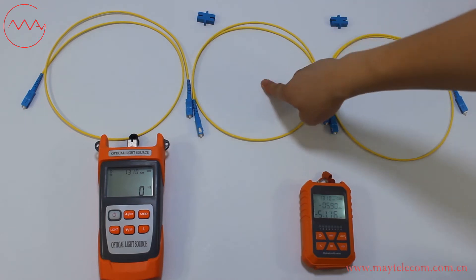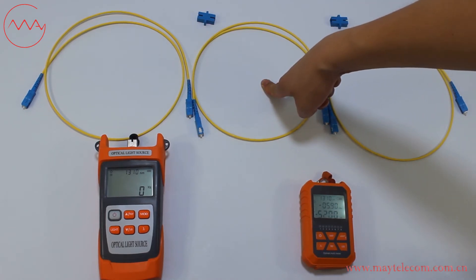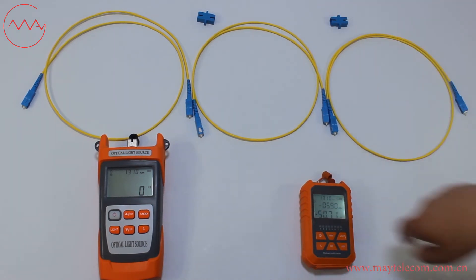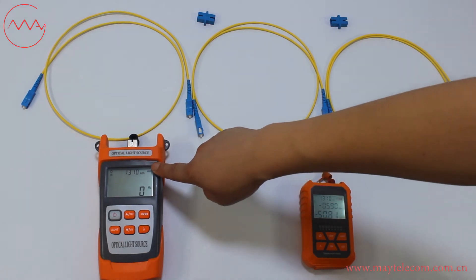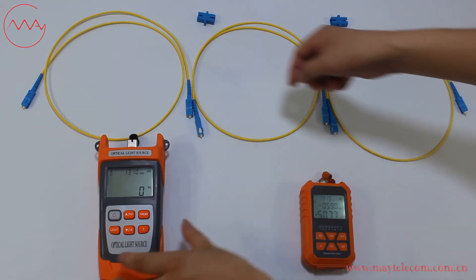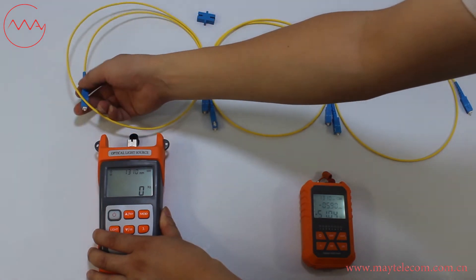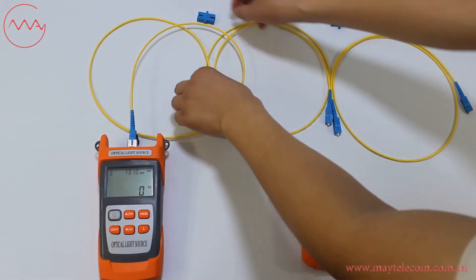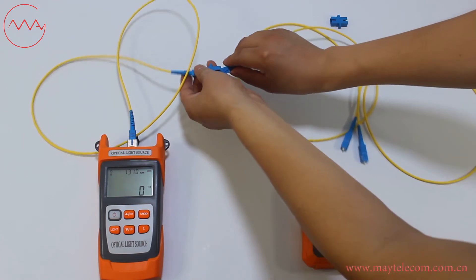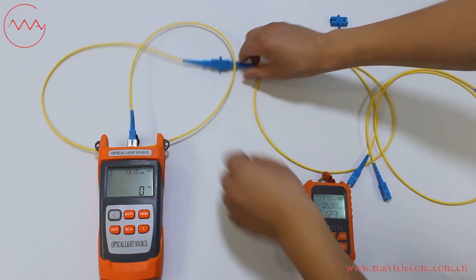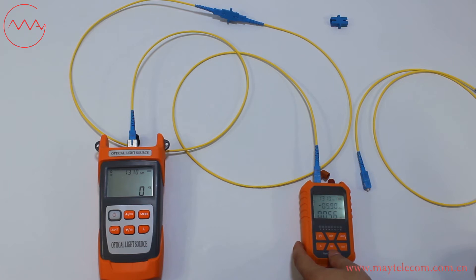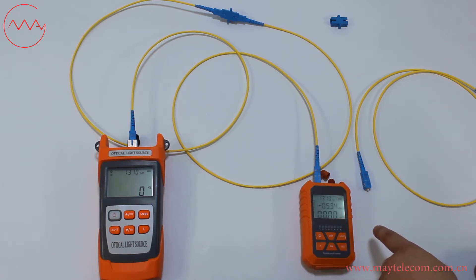This is the reference patch cord. There are two pieces of reference patch cord, patch cord and test, and SC adapters. Set the same wavelength on the optical light source and optical power meter — select 1310 nm for example. Connect the reference patch cord with the optical light source and optical power meter. Press the reference button to set 0 dB for relative power.